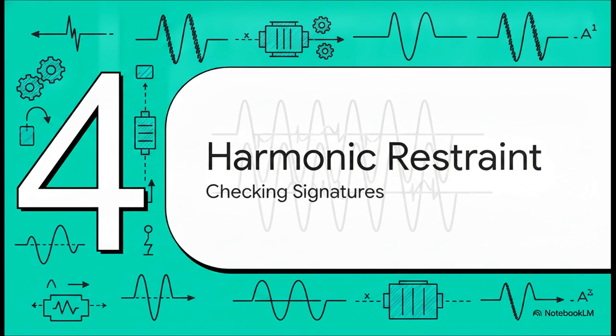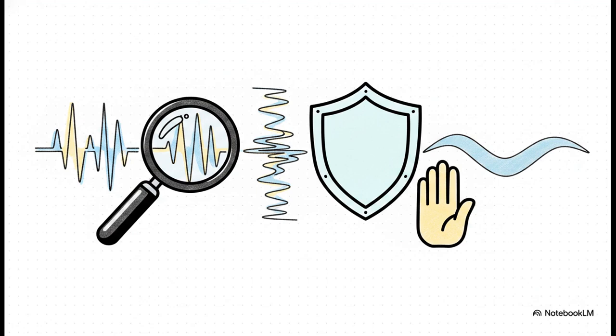Which leads us to the genius solution in Section 4, checking signatures with harmonic restraint. In plain language, the relay doesn't just look at the raw magnitude of the current. It analyzes the actual mathematical shape of the current's waveform. It turns out that massive inrush spike is highly distorted and extremely rich in a second harmonic signature. A genuine fault just doesn't look like that. Furthermore, if a transformer is overexcited, say experiencing high voltage to frequency ratios causing flux saturation, it produces a distinctly different fifth harmonic signature.